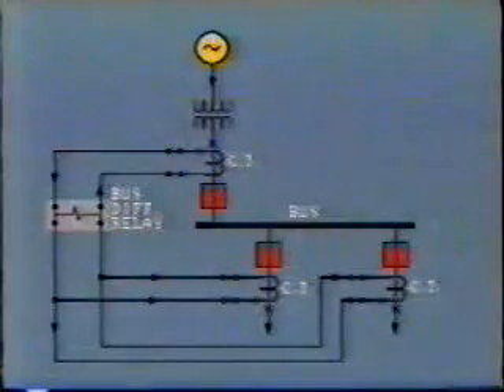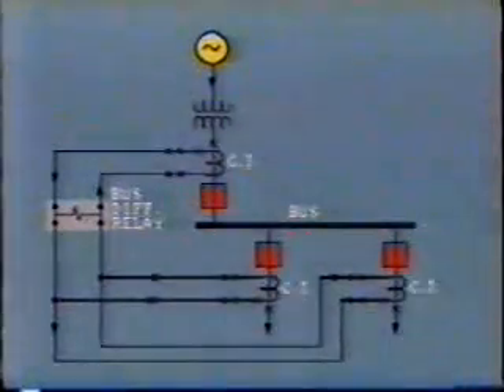As soon as possible, with load on the generator, the corresponding bus protection CTs must be checked for balance and secondary current magnitude and direction. When this test is completed, we should check at the protection relay panel that the summation of all the bus CTs is 0 or very close to 0.